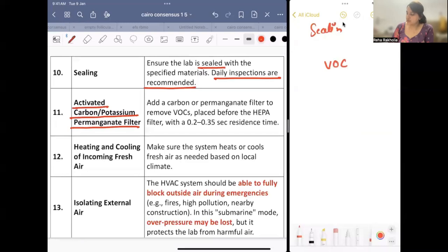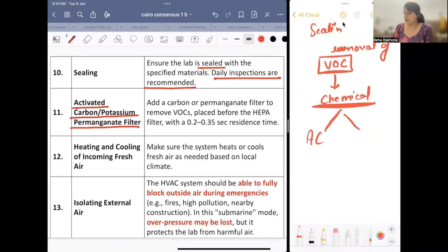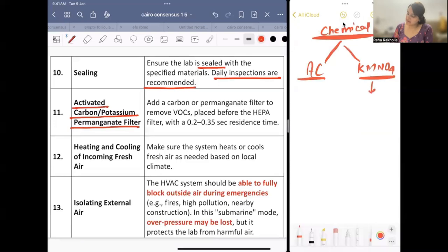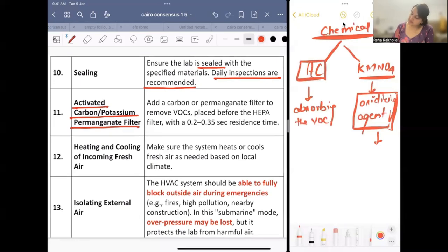For VOCs, we use a chemical filter for removal. The HEPA filter is to remove particles. In the chemical filter, what do we use? Activated charcoal and KMnO4, which is potassium permanganate. Potassium permanganate is an oxidizing agent, so it oxidizes the VOCs, and activated charcoal absorbs the VOCs.